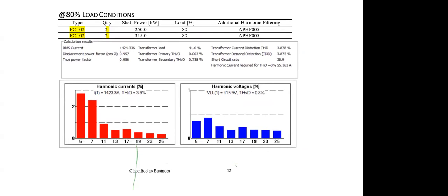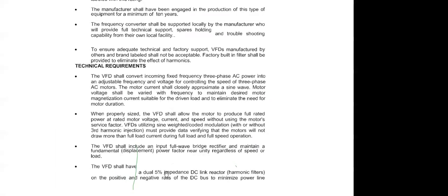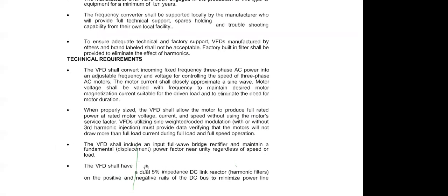So before I close, I just wanted to say one more thing. This is also important. You don't need to get carried away again by this. This is also in the bottom one. If you see that it is written, the VFD shall have a dual 5% impedance DC link reactor harmonic filters on the positive and negative rails of the DC bus. This is again a misleading statement. Misleading in the sense that this DC link reactor is not a filter. Please keep it in mind.